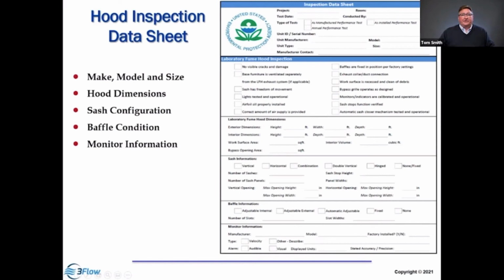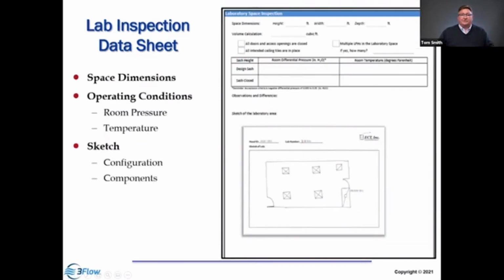And so we can go through the inspection, click the right boxes, enter your dimensions, enter the sash information, record the information about the baffles, and there's other information about the monitors and so forth. It's all right there. They also give you a form to record the information about the lab environment, the space dimensions, the airflow conditions, the differential pressure when the sash is open and closed, and it gives you a space to put in a sketch.